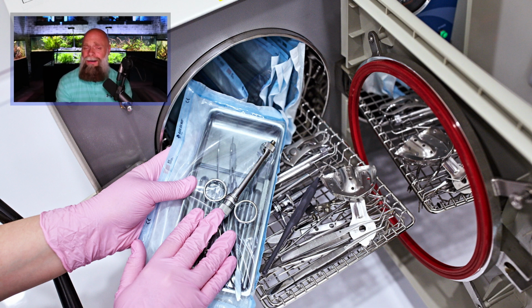For those of you who are into tattoos and piercings, a lot of times those shops will have tabletop autoclaves to ensure that some of the equipment that is reusable can be sterilized. This is, of everything we've talked about so far, the best way to sterilize something. But again, we have to make sure that what we're putting in an autoclave can withstand that high heat, steam, moisture, and the pressure. So all of our electronic devices, that's going to pretty much not be a thing here. But if you've got what we're seeing here, a lot of medical instrumentation, works out really, really well.